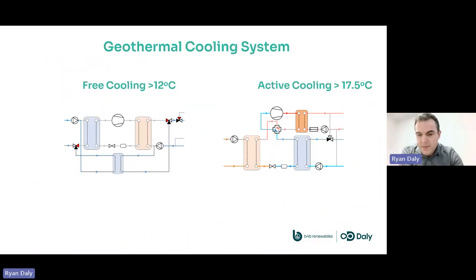Geothermal cooling is another benefit, and we'll talk again at the end about my own house and how we applied that. But with geothermal, you have free cooling and active cooling. Free cooling is basically taking the temperatures in that borehole or the ground collector, the horizontal loop, and putting that through an intermediate heat exchanger that then is being delivered directly into your fan coils or your underfloor heating system. So it's taking that temperature of 10, 12 degrees in the ground and basically transferring that into your heat emitter.